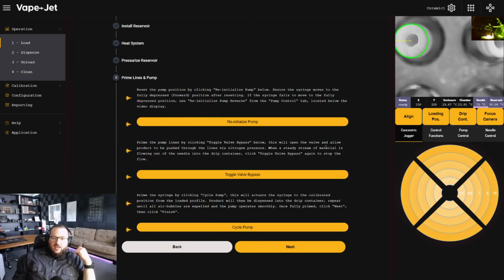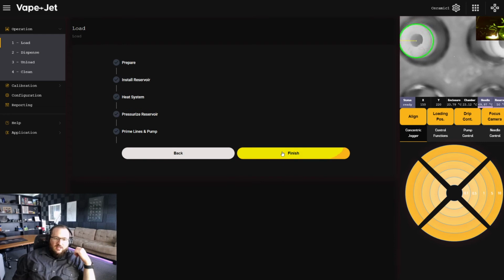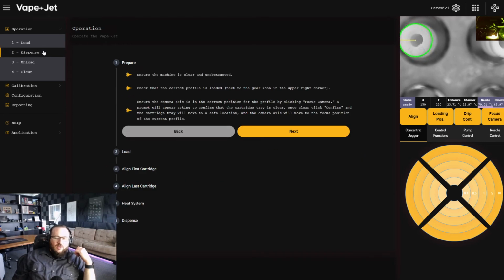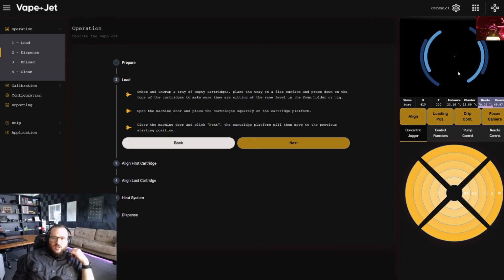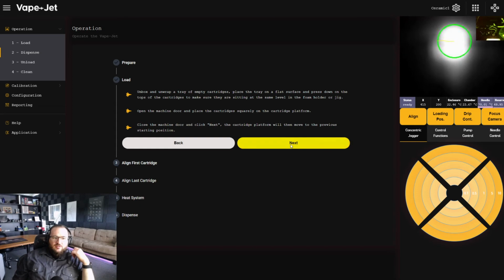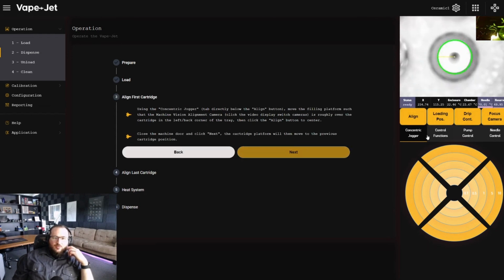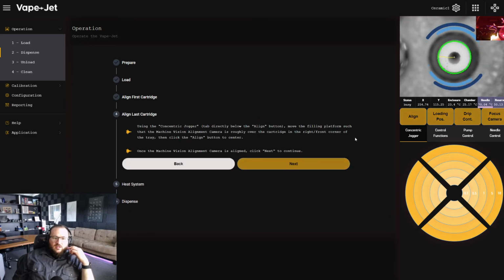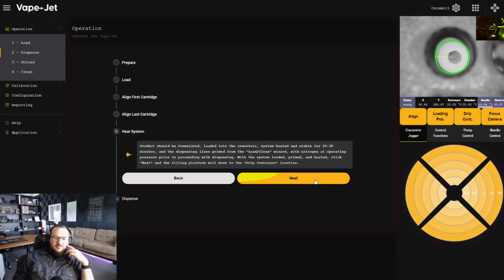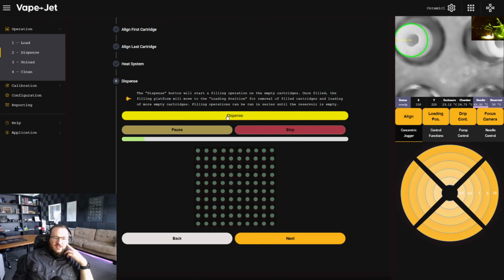Then you need to prime the lines and pump. Again, it's all software based. There's no physical adjustments needed here. And all the buttons that you need are brought right to the operator. Once this is done, you hit next and finish. And we're going to go straight to dispense. So the Dispense Wizard, now that the canister is loaded, is going to walk the operator through loading the machine. So placing an empty tray of cartridges on the tray. Lining it up real quick by showing it where the first and the last cartridges are. Ensuring that the product is heated up. And then moving on to the Dispense Wizard.